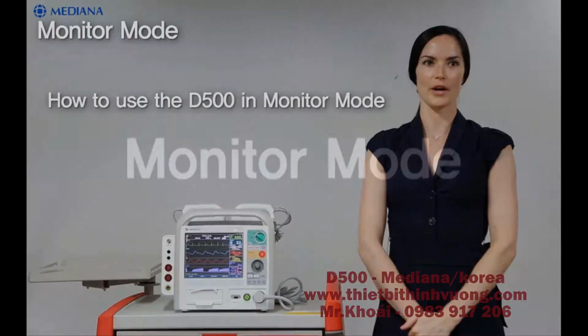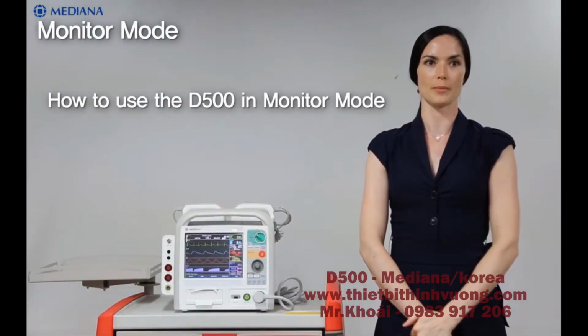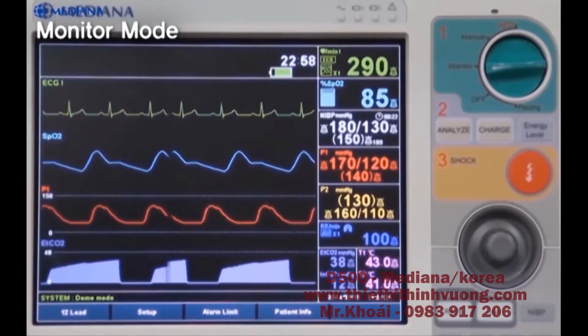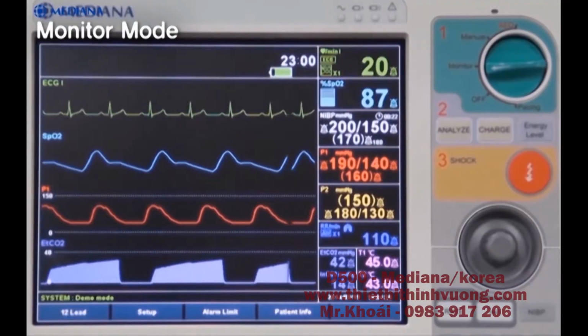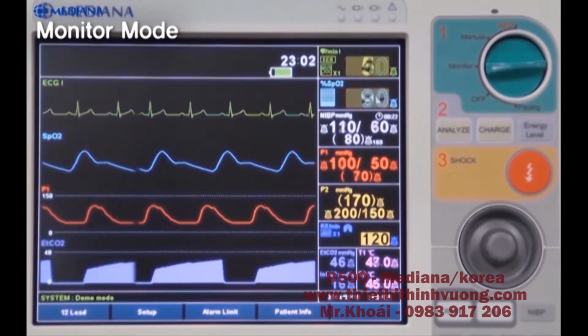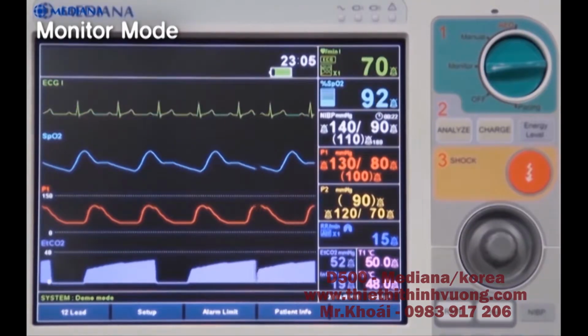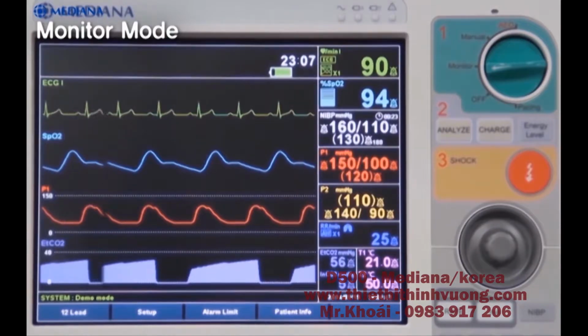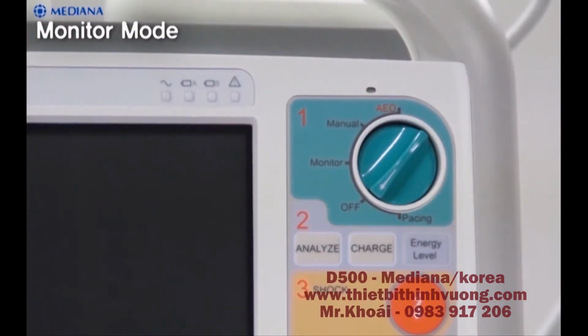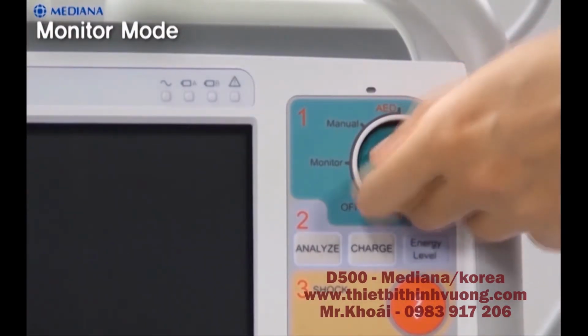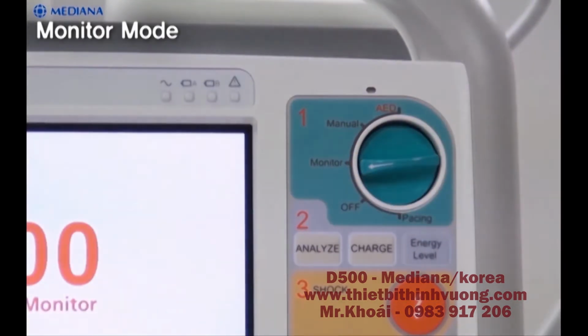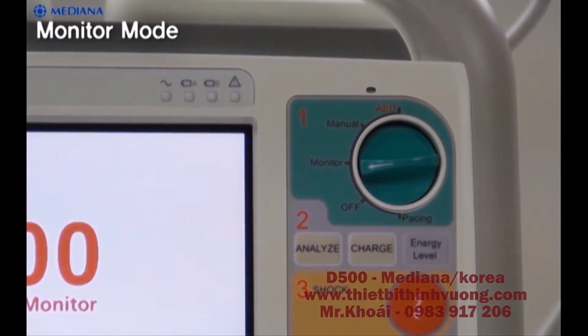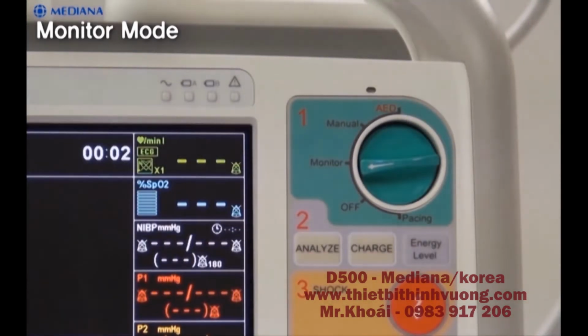Monitoring mode. Now, let's see how to use the monitor mode. The D500 manual defibrillator provides the monitor mode to view the ECG waveform, the heart rate, pulse rate display, NIBP, SPO2, respiration, temperature, IBP, and capnography monitoring. If you want to use the monitor mode, turn on the monitor mode by rotating the mode select knob after connecting the accessories. Then, verify that the monitor mode is activated normally.